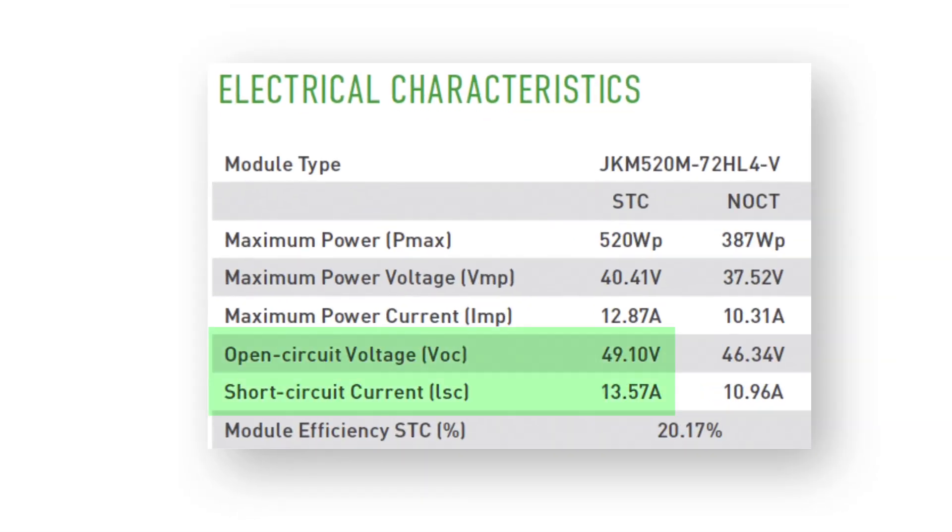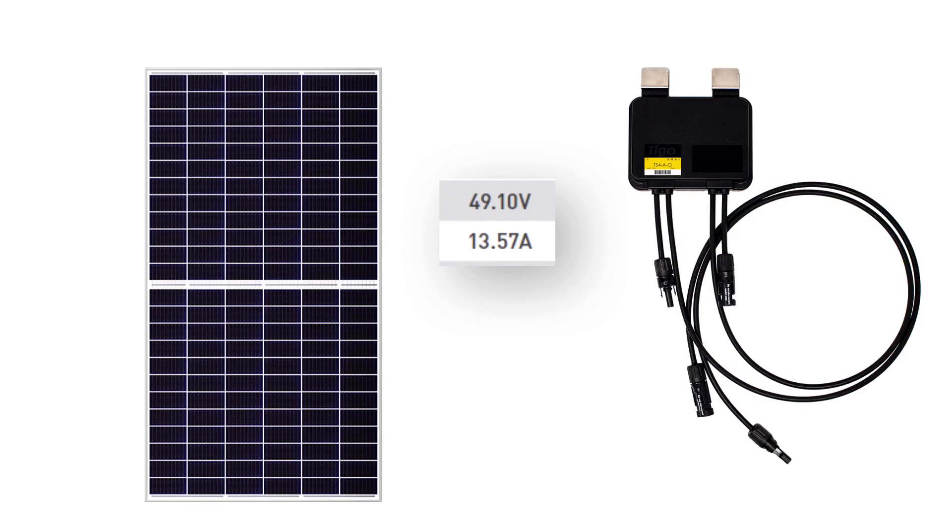We must use the VOC and ISC values from the datasheet since they represent the worst-case scenario of voltage and current that could ever enter the TS4 terminals from the PV module.